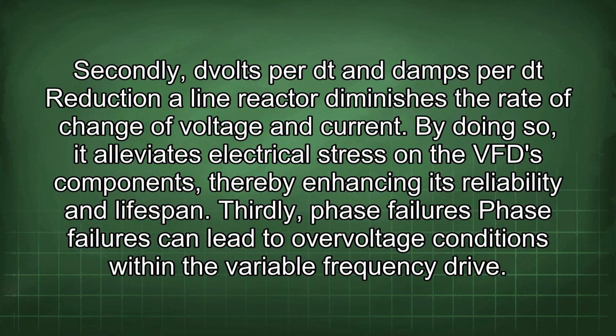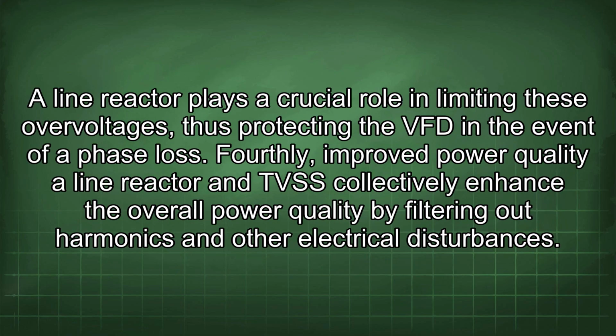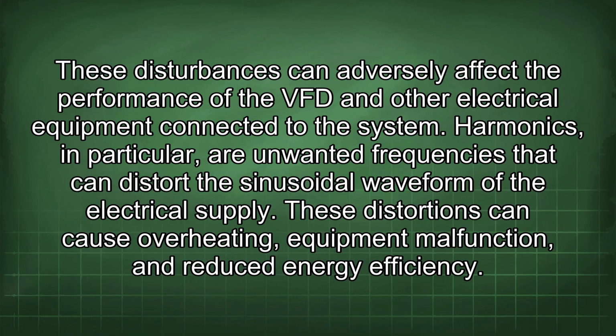Thirdly, phase failures. Phase failures can lead to overvoltage conditions within the variable frequency drive. A line reactor plays a crucial role in limiting these overvoltages, thus protecting the VFD in the event of a phase loss. Fourthly, improved power quality. A line reactor and TVSS collectively enhance the overall power quality by filtering out harmonics and other electrical disturbances. These disturbances can adversely affect the performance of the VFD and other electrical equipment connected to the system.